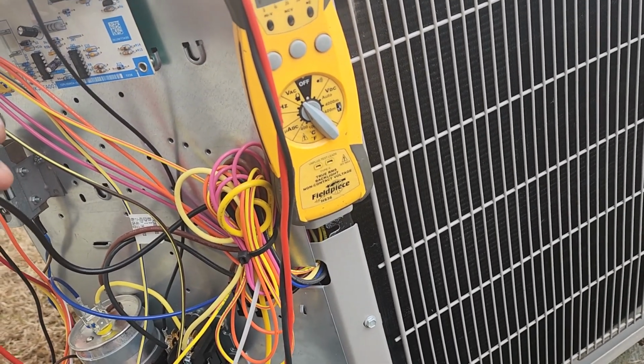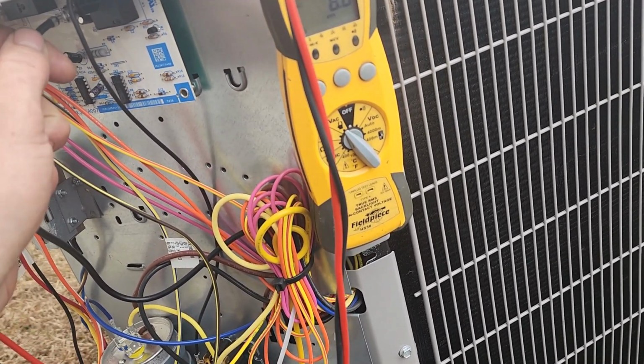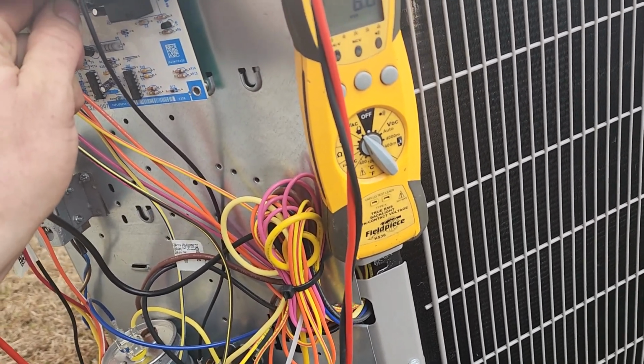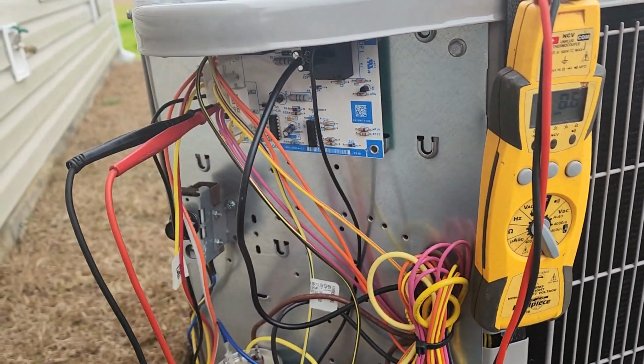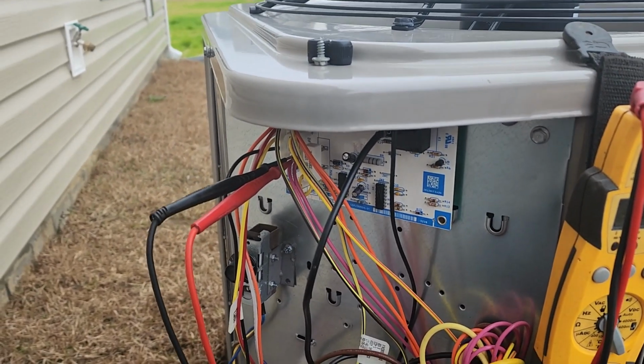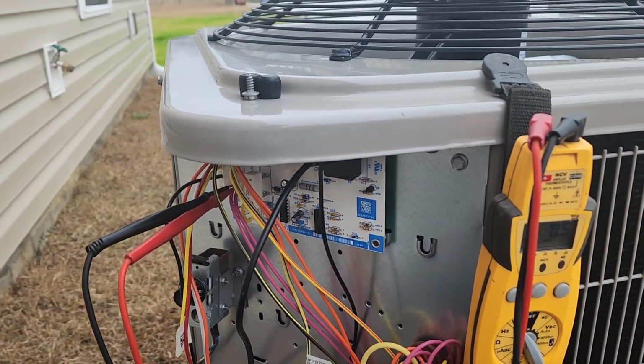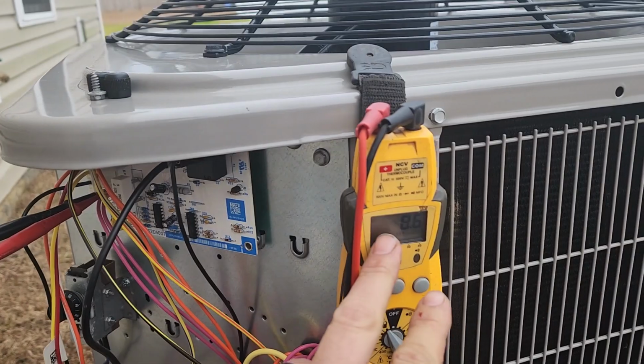Sounds like a pretty normal defrost to me. Get our fan plugged back in, see when it comes out of defrost what we got there, and make sure that sensor reopens.